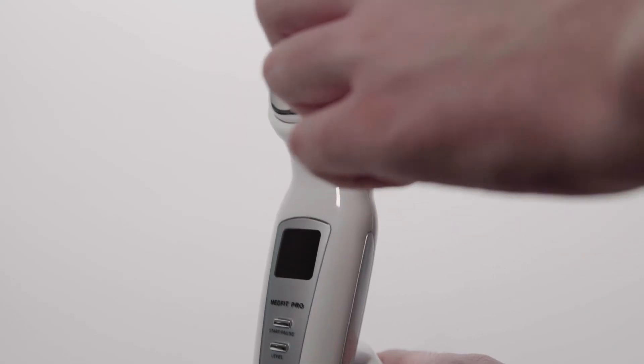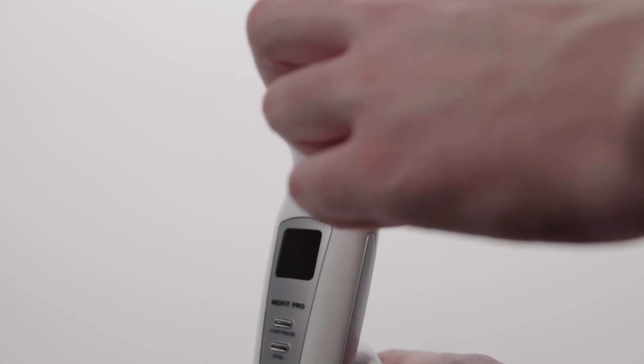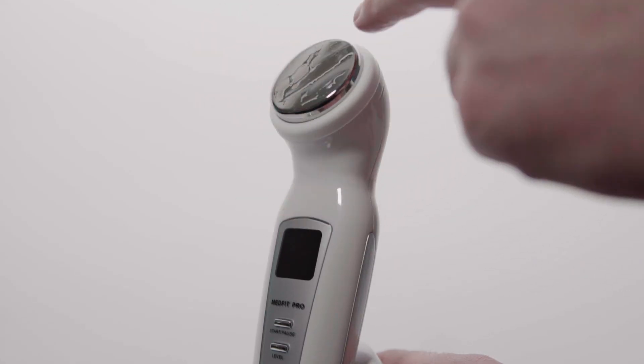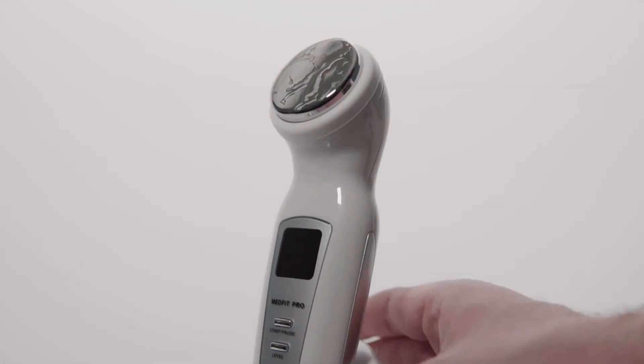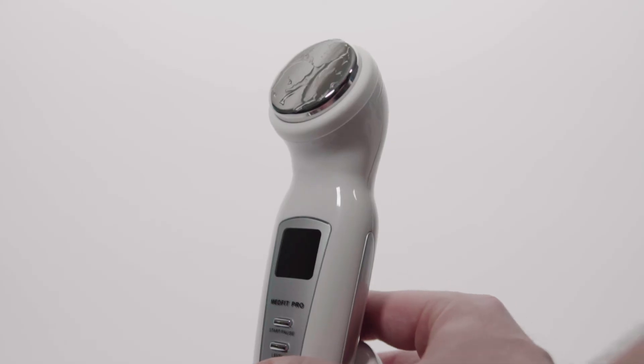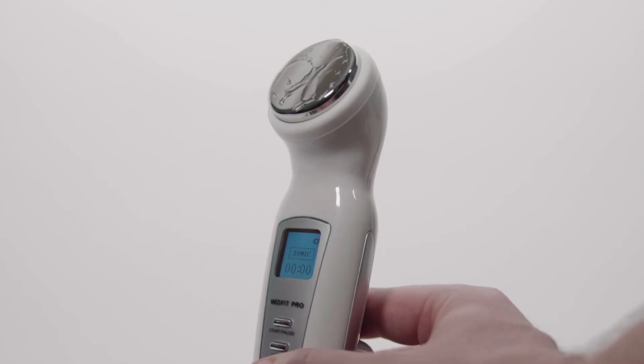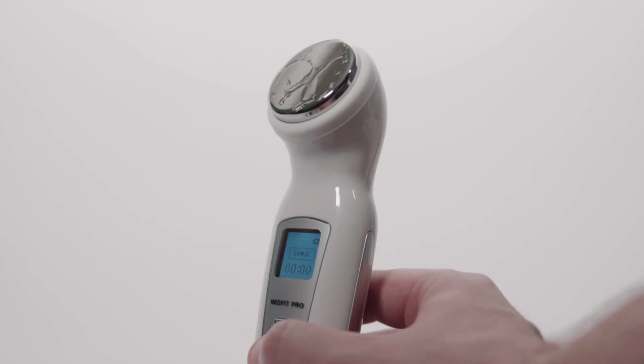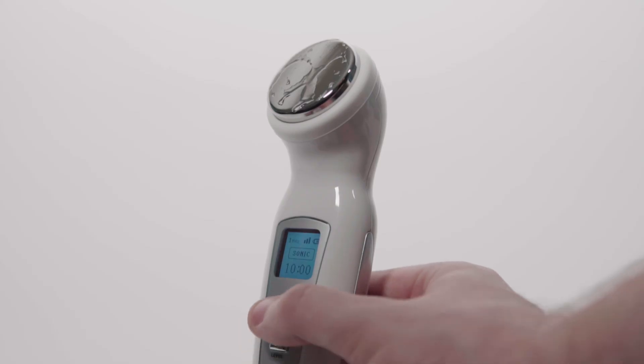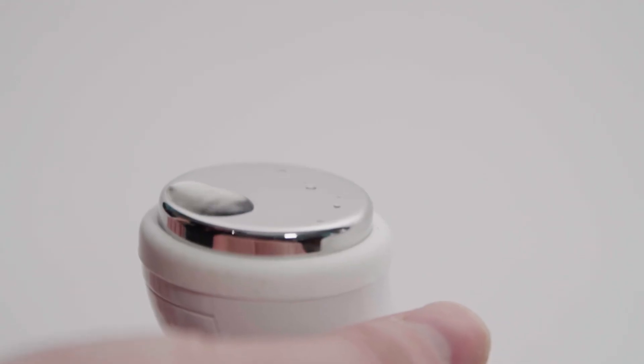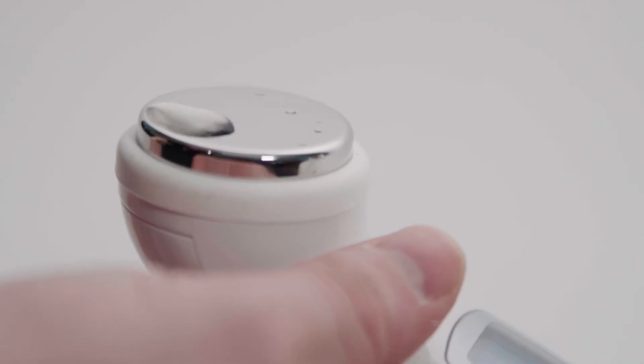It is also recommended that you test the output of your ultrasound on a regular basis. Place a small amount of water onto the transducer head and turn the intensity to high. You will note a vibration in the water with a small amount of water displacement.